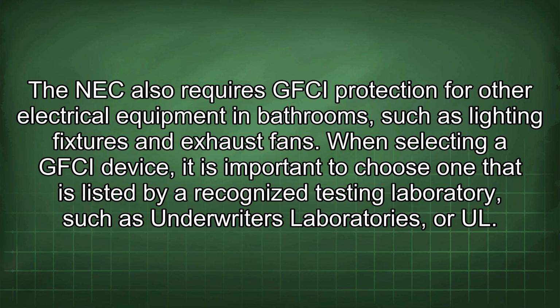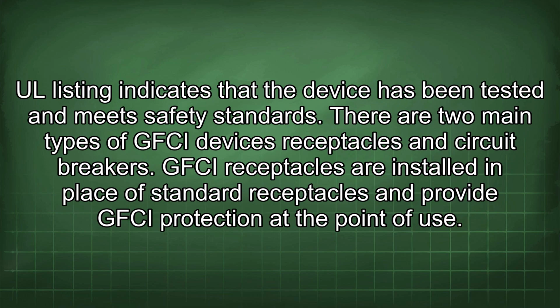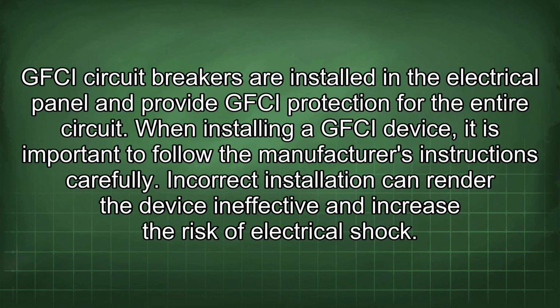When selecting a GFCI device, it is important to choose one that is listed by a recognized testing laboratory, such as Underwriters Laboratories or UL. UL listing indicates that the device has been tested and meets safety standards. There are two main types of GFCI devices: receptacles and circuit breakers. GFCI receptacles are installed in place of standard receptacles and provide GFCI protection at the point of use. GFCI circuit breakers are installed in the electrical panel and provide GFCI protection for the entire circuit.